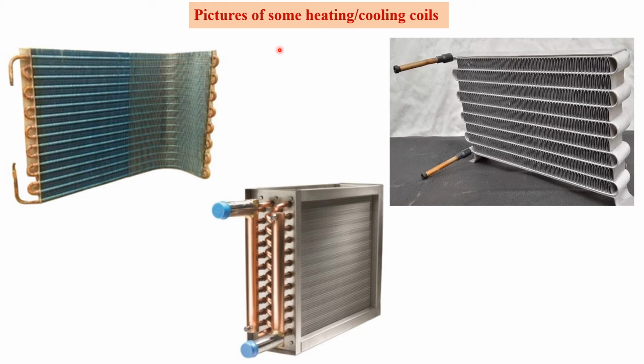Here you can see some real pictures of heating or cooling coils which are used in air conditioning equipment. You can see here a copper pipe which has multiple folds. Each pipe is separated from the next one, and they also have fins mounted over them, so that the flow of air over these tubes is uniform. In this picture also, these are the fins which are placed between the series of tubes. These are the tubes which carry either the refrigerant or some hot fluid. If air is required to be sensibly heated, hot water will flow through them, and if it is to be sensibly cooled, they will carry chilled water. The tubes may have a single pass or multiple passes, so there may be multiple rows of cooling or heating coils.